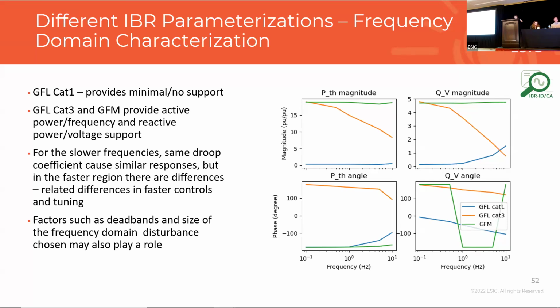Dead bands are fairly minimal in the way we've looked at it. So if you have a slow moving event, category 3 and the GFM resource are able to provide the service. Category 1, nothing at all—the axis stays at 0, indicating that any kind of frequency or angle change on the system, that resource is not going to change its power output. It's going to try to maintain its pre-disturbance power output and not do anything for the network.